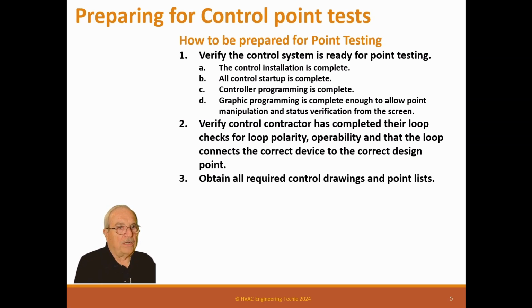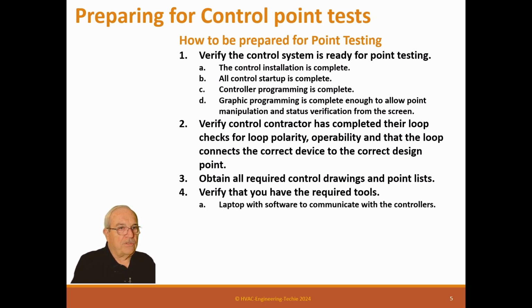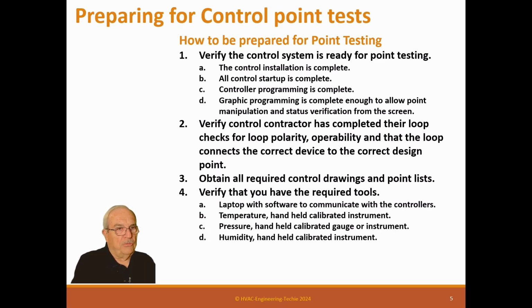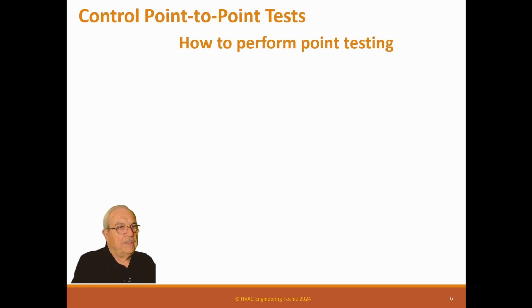Obtain all required control drawings and point lists. You need to have that. Verify that you have the required tools. Laptop with software to communicate with the controllers. Temperature, handheld calibrated instrument. Pressure, handheld calibrated gauge or instrument. Humidity, handheld calibrated instrument. CO2, handheld calibrated instrument. Electrical meter, true RMS volts and amps. Then you have those tools. They're calibrated. They're your tools.